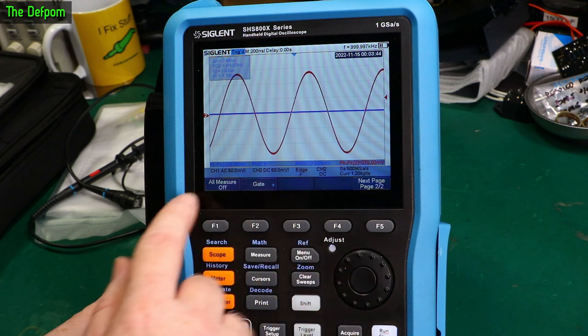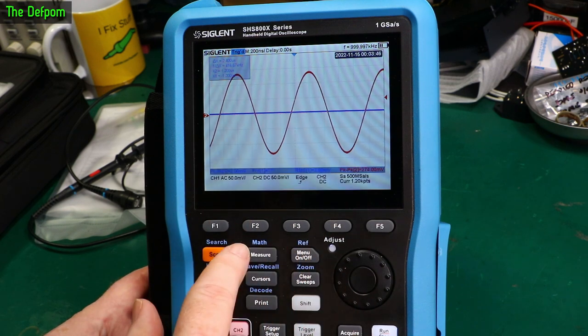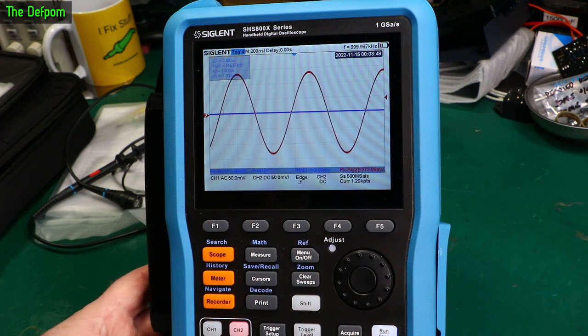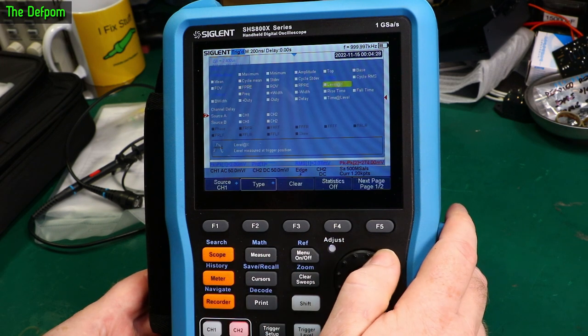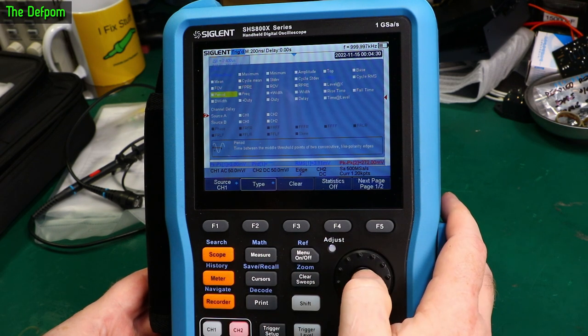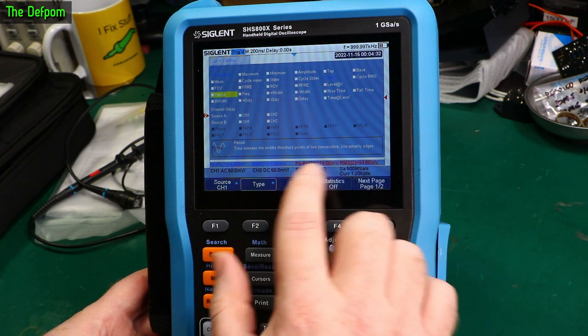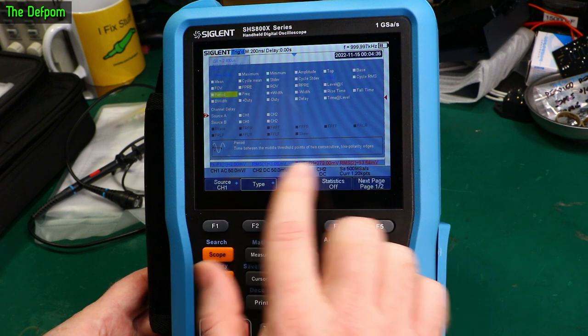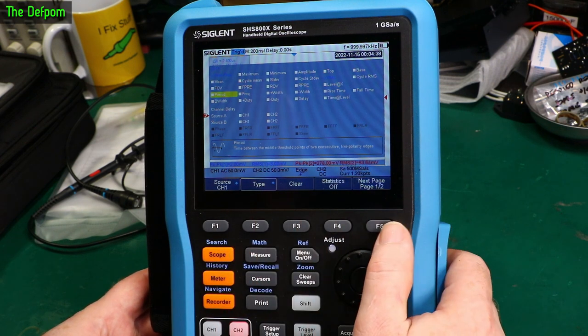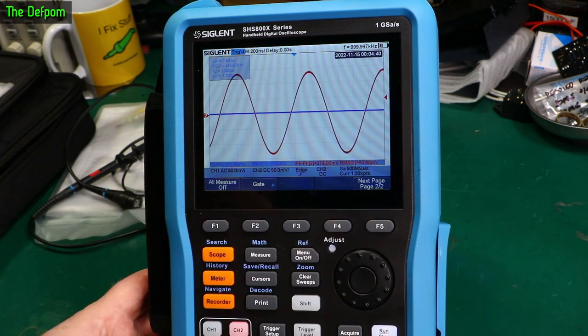Where's the RMS one? Is it underneath the menu? Huh. Okay. Right. Yeah. Turn period off. Get more room for the other ones. There we go. It's wrapping over. So even though it was enabled I couldn't see it on screen because there wasn't enough real estate for it. So that's fine. So now we can do. And this channel 2 is also giving about the same value. If anything it's reading slightly lower.